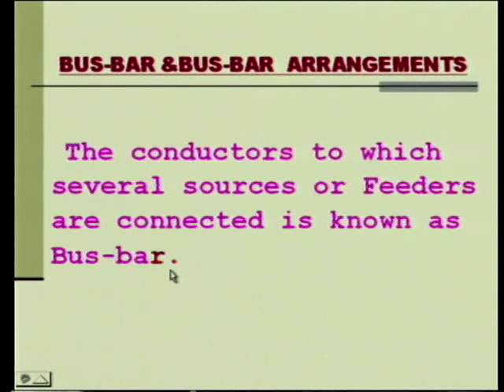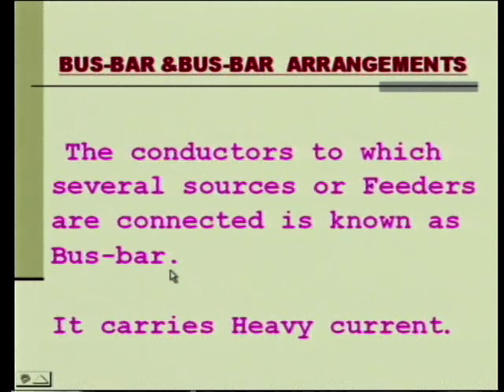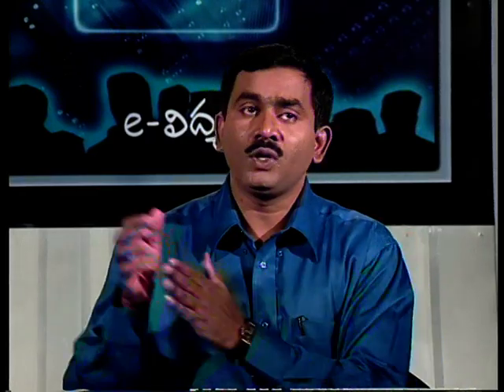The conductors to which several sources or feeders are connected are known as the bus bar. It carries heavy current, just like an APSRTC bus carries passengers. But in our power system, it draws the current based on load demand. It takes the current from the generators and gives the same to load centers. Generally, bus bars have different ratings. The conductors used in bus bar systems are ACSR conductors. In a substation, these are namely panther conductors, zebra conductors, and dog conductors. These are some examples of ACSR conductors used in different stages of a power station.